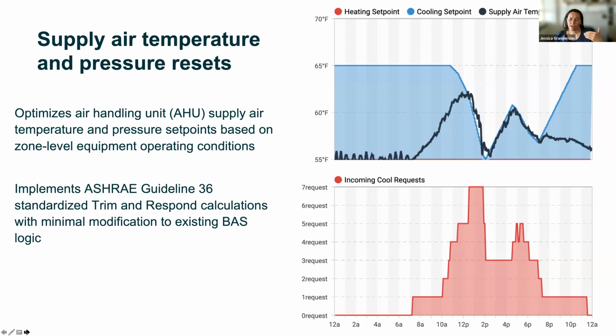On the top plot, the cooling set point is shown in light blue, the supply air temperature in darker blue. On the bottom are the incoming cooling requests. As the cooling requests mount and grow across the day, the system responds: the cooling set point drops and the supply air temperature responds accordingly. This is the strategy in action, delivered through the analytics interfacing with different makes and models of control platforms.